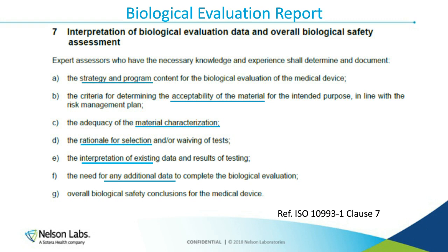And then the need for any additional data. What we've seen often is that we'll be doing this testing with clients and they call us because something has happened. Maybe a failure, or maybe something was identified in the chemistry testing, and we need to do some more targeted analysis. This is where we have that conversation. This discussion happens throughout the testing phase, but it needs to be explained here in the biological evaluation report so there's an understanding of why the additional testing was done and whether the overall risk was eventually mitigated. At the end, we make an overall conclusion about the biological safety of the medical device, putting everything together to determine if all of the risks were addressed and if the data is appropriate and accurate.